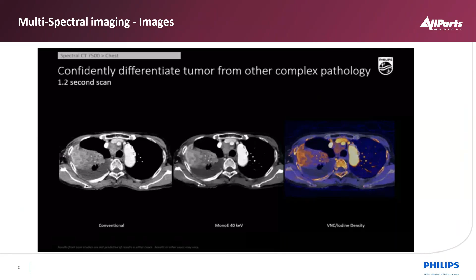So then we move into photon counting CT. When we talked about dual energy kVs, we're basically at 80 kV and 140 kV. Now, what if we could define other kVs too? When we produce an X-ray beam out of the X-ray tube, that X-ray beam has a number of different energy levels in it. The peak would be maybe our selected kV, maybe even a few photons over. So for instance, if I selected 120 kV, I could have some X-ray photons that are even more energetic than 120 kV, and then quite a few are less than that energy.